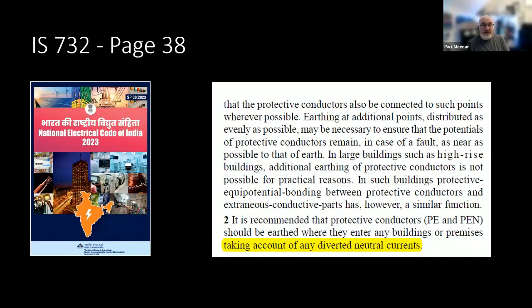Just worth noting, on Indian Standard 732, page 38, it actually mentions diverted neutral current 3 times. So it's quite interesting where protective earth or PEN conductors should be earthed where they enter any buildings or premises. Taken into account, configuration is key. You may want to think, well, what do I bond? Where do I bond? How do I earth it? Do I introduce a greater level of diverted currents?